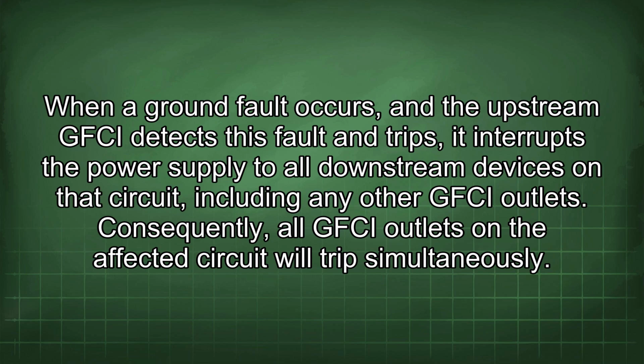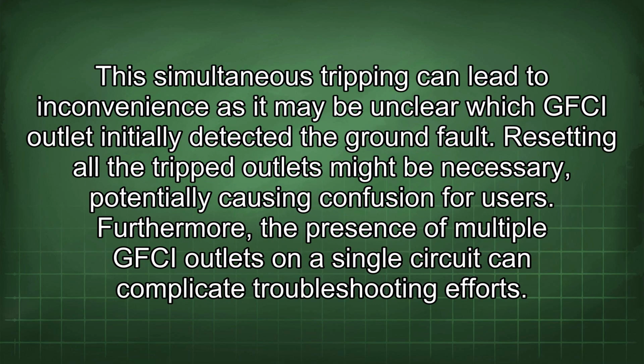When a ground fault occurs, and the upstream GFCI detects this fault and trips, it interrupts the power supply to all downstream devices on that circuit, including any other GFCI outlets. Consequently, all GFCI outlets in the affected circuit would trip simultaneously. This simultaneous tripping can lead to inconvenience, as it may be unclear which GFCI outlet initially detected the ground fault. Resetting all the tripped outlets might be necessary, potentially causing confusion for users.